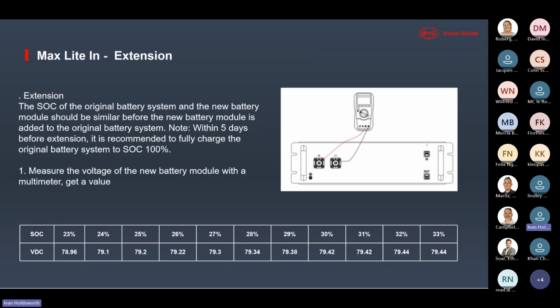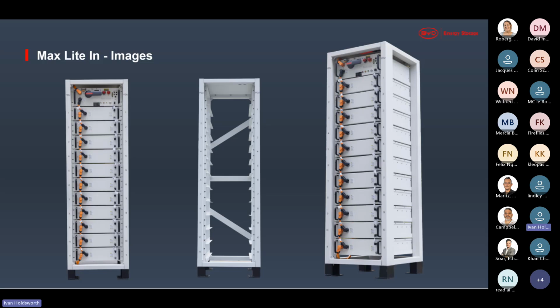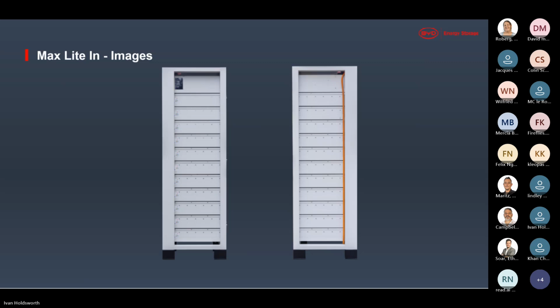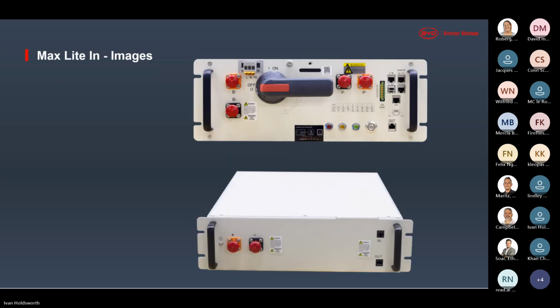And here we can see the process for extensions and making sure your batteries are all at the same voltage and the same SOC. And here are some images of the Max Lite and the Max Lite tower. That's a tower of 11 modules, and that will be about 850 volts, and your operating voltage will be up to about 1,000 volts. You can see the image from the back, and some images of the PDU and the battery module.